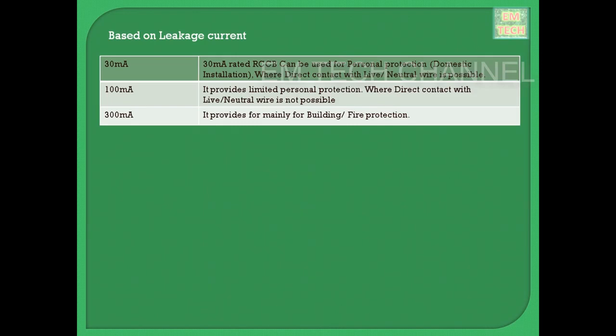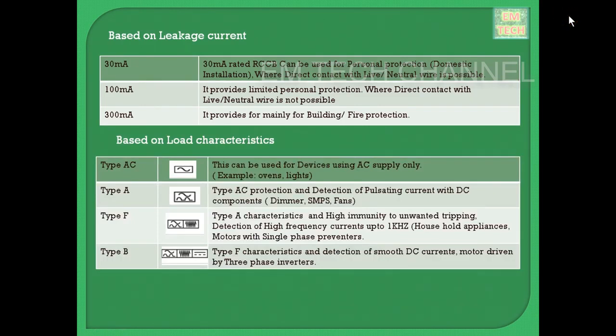A 300 milliamps rated RCCB is not used for personal protection. It is used only for building protection and fire protection. And the fourth factor that we discuss in this video is the load characteristics. Based on the load characteristics, RCCBs are classified into 4 major types: type AC, type A, type F and type B. We will discuss them one by one. The symbols in the second column of the table represent the load characteristics. This printing is mandatory and will be printed on almost every RCCB.